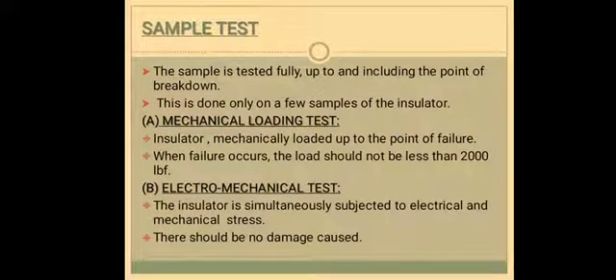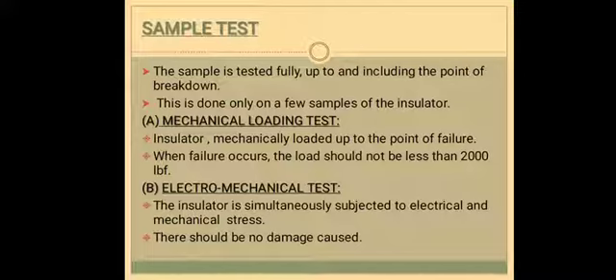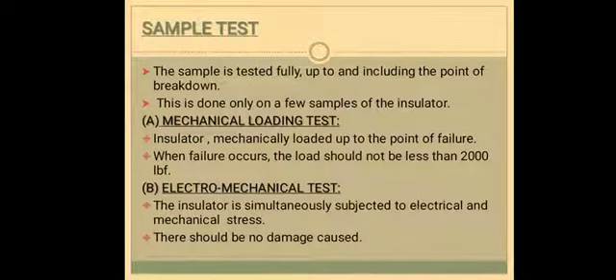Next type is the sample test. The sample test is tested fully up to and including the point of breakdown, done only on a few samples of the insulator. The first type is the mechanical loading test — the insulator shall be mechanically loaded up to the point of failure. This is a bending test applicable to pin type as well as line post insulators. It will be subjected to three times the specified maximum breaking load for one minute. There should be no damage to the insulator; in case of the post insulator the permanent set must be less than one percent. The load will be raised to three times and there should not be any damage to the insulator and its pin.